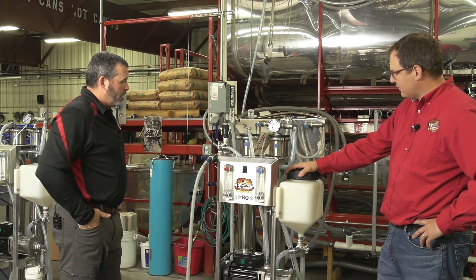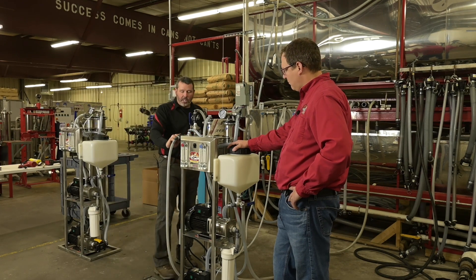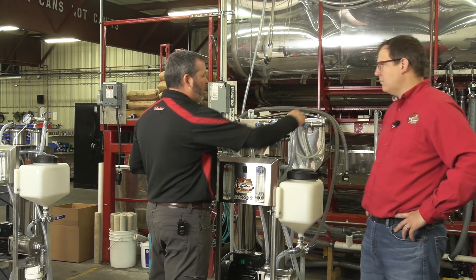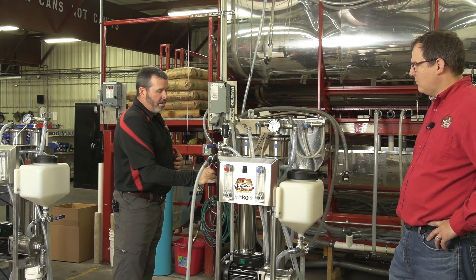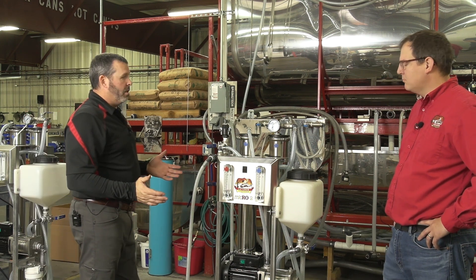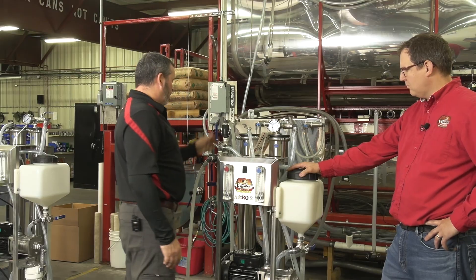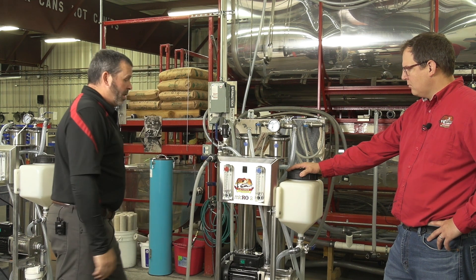Tell me about the rinse cycles and the wash cycles of this machine. So rinse cycle is pretty easy — it's just a matter of a flip of a valve. As we look at it right now, it is actually in rinse cycle. If we just want to put it into concentrate mode, we're going to close this valve here, turn this valve, and turn this valve. And that's it — we're in concentrate cycle now. Simplicity. It's very simple. To go to rinse mode again, switch this valve, this valve, and you would open this valve. And now we're in rinse mode.